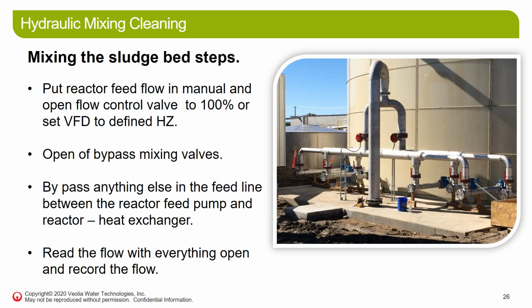So what you can do here is put the reactor feed flow in manual, open the flow control valves, if there is one, to 100%, or set the VFD to a defined percentage. Open any bypass mixing valves, and bypass anything else in the system. Say there's a heat exchanger or some other thing that's causing resistance. You want to flow through the system with the least amount of resistance and record everything with the flow open.